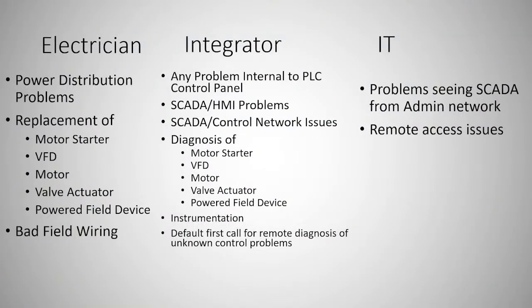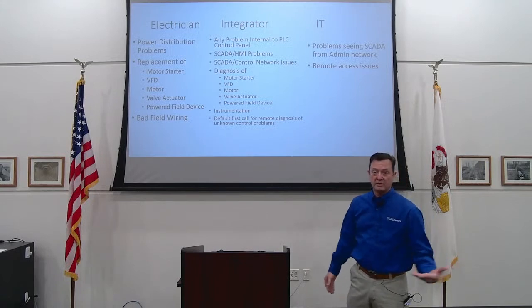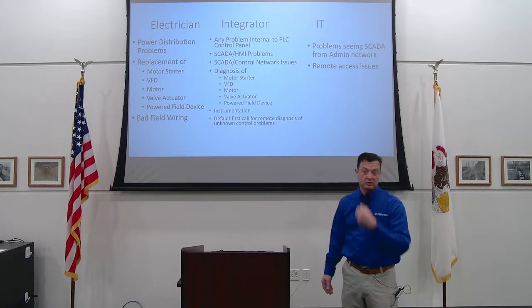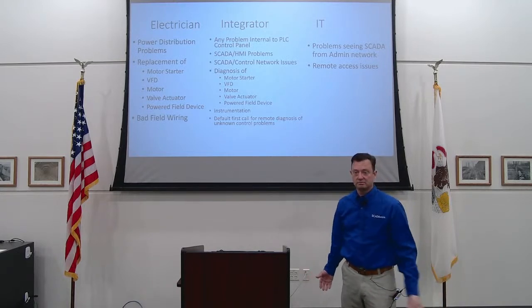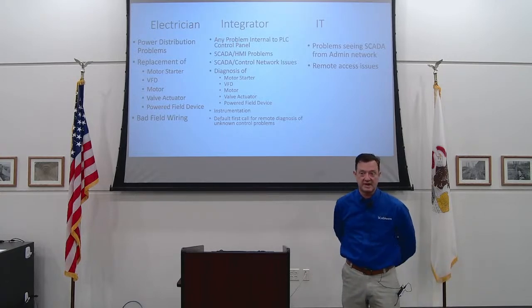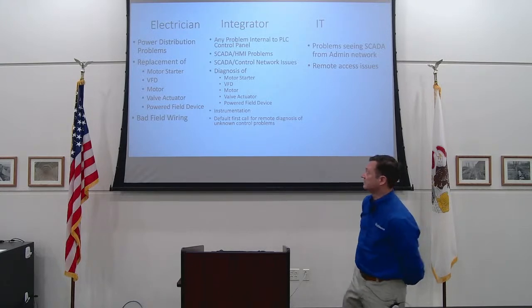The electrician is going to handle power distribution problems, replacement of devices, and the actual repair of bad field wiring. An integrator is going to handle the diagnostic stuff and instrumentation, and I would consider the integrator the default to call first. If you have a problem and no idea where the source is, an integrator is probably going to identify it faster. The other advantage to having an integrator do it is remote access to your site. If networks are still working and we can get into a PLC, we can normally identify problems without making the trip on site and say, hey, you've got a bad pressure switch on this pump. So there's a lot of value in that from a cost perspective as well.